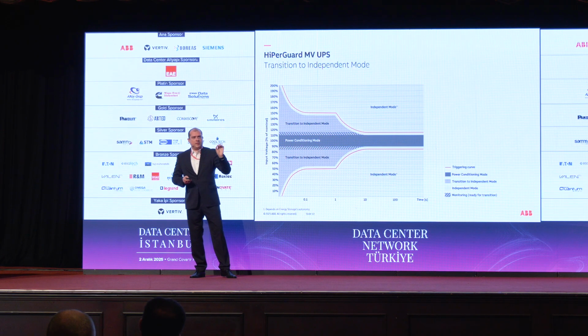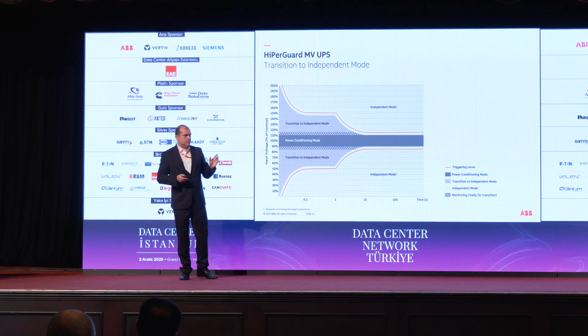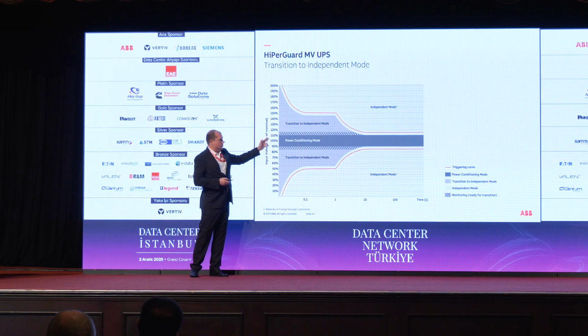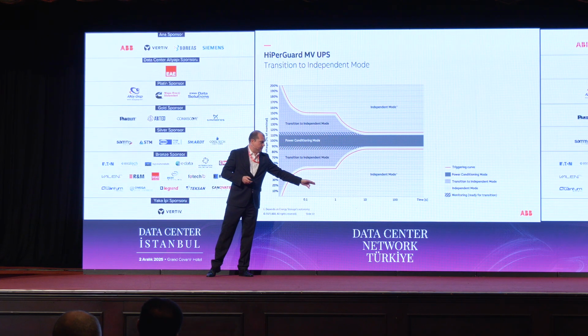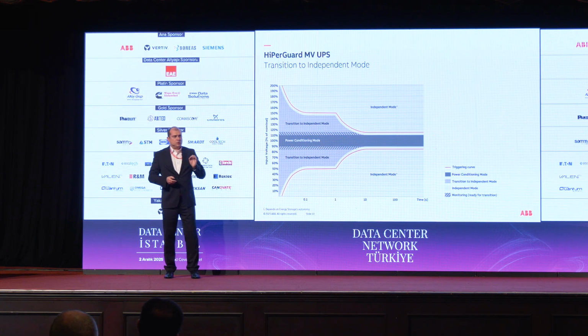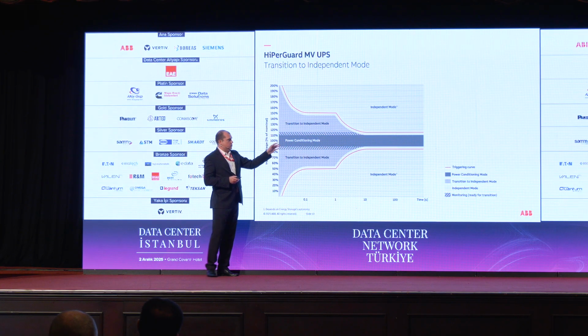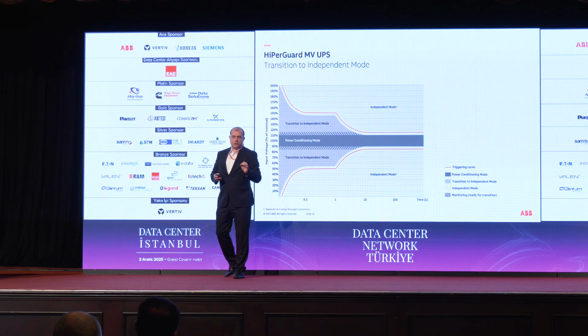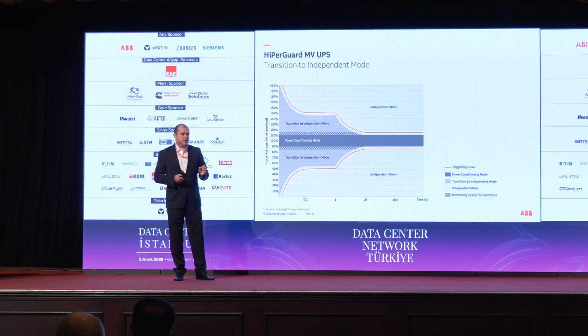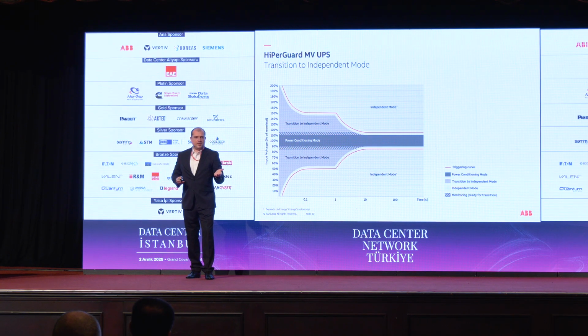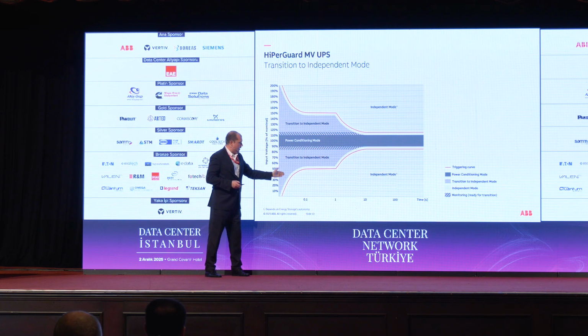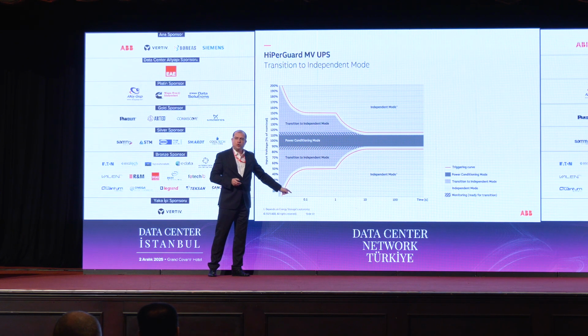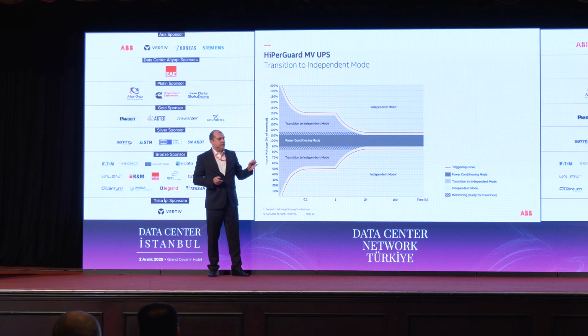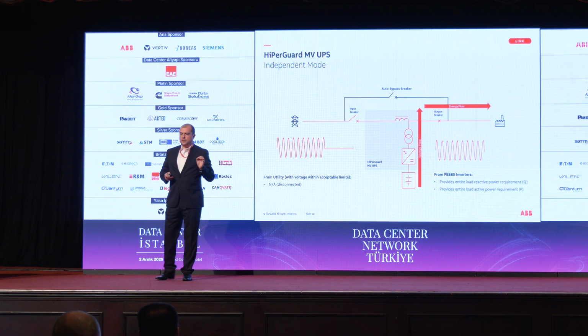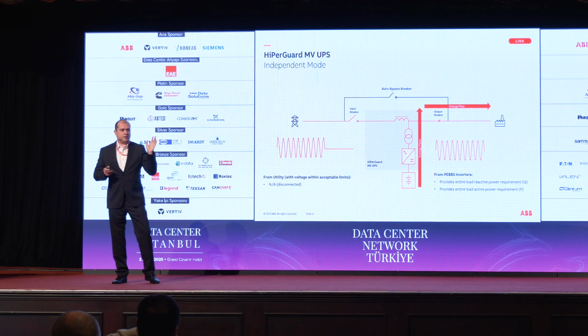We observe all of the anomalies happening on the input side. All of those can be depicted in terms of a nominal voltage and in terms of a duration, here indicated in logarithmic scale. As long as any event, dip, sag, swell, or anything else falls within these red curves, the system continues to run on the grid without any issue. However, if you have an unfavorable event, such as a short circuit, for example, it means voltage is collapsing down to zero, and we have crossed this threshold, this red line. What we do, we immediately open the input circuit breaker. And by doing so, we decouple ourselves from the grid.